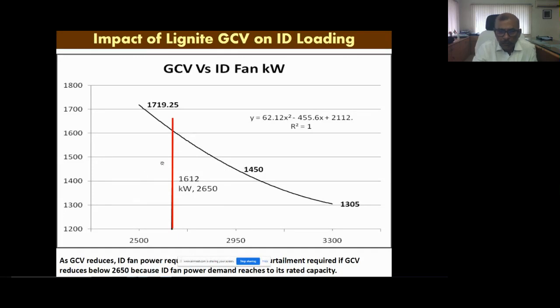So in this graph, which is GCV versus the ID fan kilowatt, you see, if you go below 2650 GCV, this becomes a choking point. Then you cannot go for the full load, and the only option left is to reduce to partial loading. Then only the ID fan can take it. Otherwise, from this red line, you will not be able to generate more than this, because the fuel quality has gone down, and that is natural also.